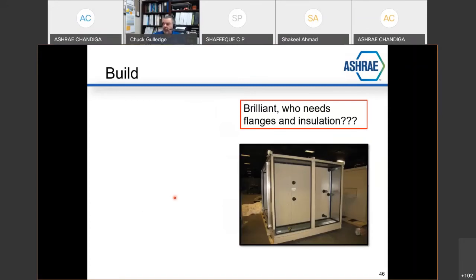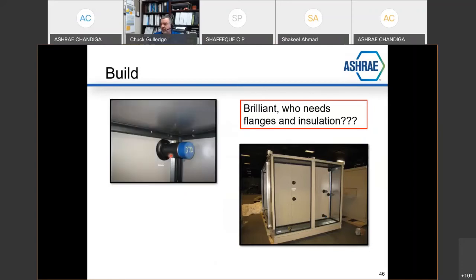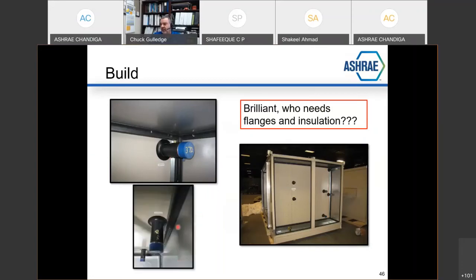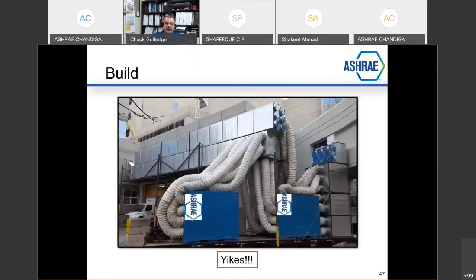Another modular air handler. These happen to be chill water coils, big unit, stacked chill water coils. Well, this might be an interesting development. That right there is a blow up of that. Look how close that is to the wall. That was 2.5-inch piping. There is no way to get a flange on this, to go to flanged piping, and there's no way to get in here and insulate this with, I think that required two-inch insulation to get to it. How do you work on it? Big disconnect. Yikes. So don't do things like this in your design practices.